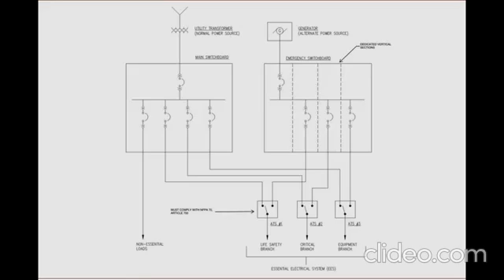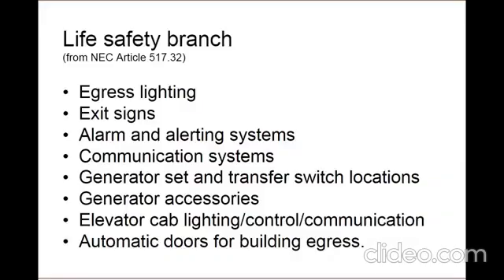In addition, there's new verbiage in these codes that state, for the purposes of this code, the life safety branch must comply with Article 700, which is emergency systems, in the NEC. This was added to clarify the relationship between Articles 517 and 700 of NFPA 70, so that it's intended that only the life safety branch of the EES comply with Article 700, not the critical and equipment branches.